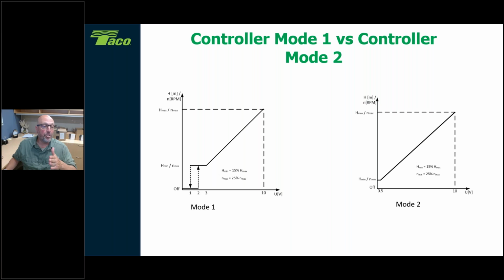And then therefore, once you get down to 1 volt and below, then it shuts off. So you have a minimum speed the pump runs at. That's your mode 1. Mode 2 is a minimum that you're programming here. All right, and it never shuts off completely except for the on-off enable switch coming in. So mode 1 does not need an enable switch. It does it via the 0 to 10 signal. Mode 2 does have to have an enable switch. So excellent question, Darren. Thank you very much.